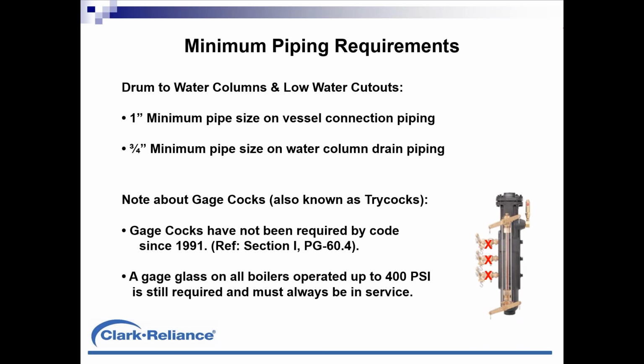These valves, when they fatigue, can leak, they can drip hot water. Since 1991, the code looked at the reliability of gauge glasses and simply eliminated trycocks as not required, and you can get by with only 1 gauge glass if you wish. Having said that, we still have a lot of users in plants who continue to use those 3 trycocks. We still sell them, but they have not been required since 1991.